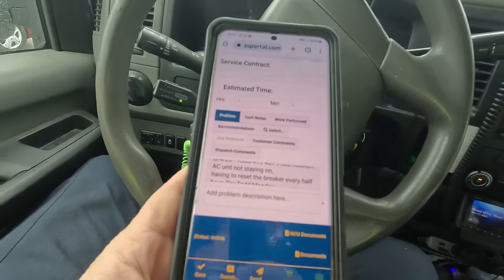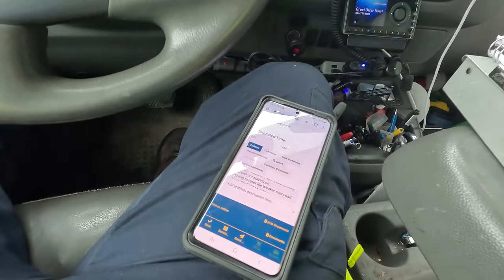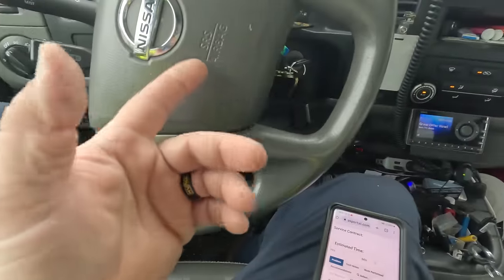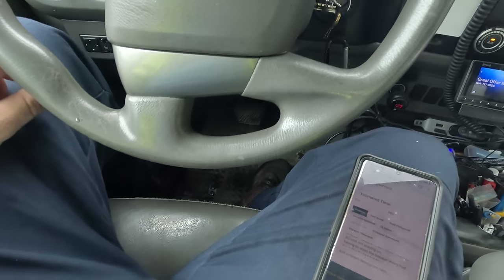We're going to order and see if we can get two motors authorized to be replaced. Right now the unit is running and the refrigerant charge looked to be fine. Reset the codes — if we come back and it has a low pressure switch fault again, then we know we've got a fan motor failing and we'll need to have that replaced. I hope you enjoyed the video — if you want to see more like it, give it a thumbs up. Consider subscribing, and we'll catch you on the next one. They were having to reset the breaker every half hour — so the question is, was it tripped or were they just resetting the unit? It would have been resetting the unit.